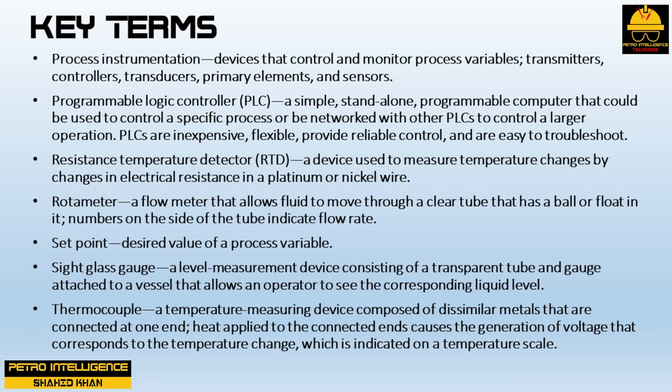Process instrumentation devices control and monitor process variables: transmitters, controllers, transducers, primary elements, and sensors. A programmable logic controller (PLC) is a simple standalone programmable computer that can control a specific process or be networked with other PLCs to control a larger operation. PLCs are inexpensive, flexible, provide reliable control, and are easy to troubleshoot. A resistance temperature detector (RTD) is a device used to measure temperature changes by changes in electrical resistance in a platinum or nickel wire.